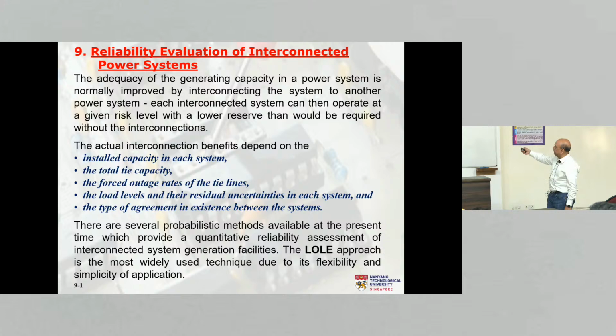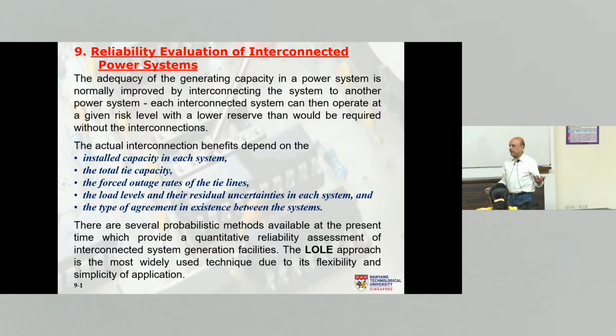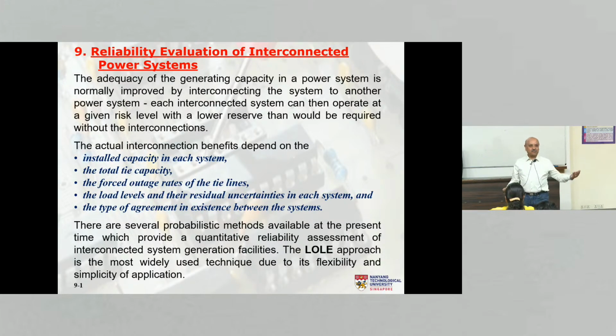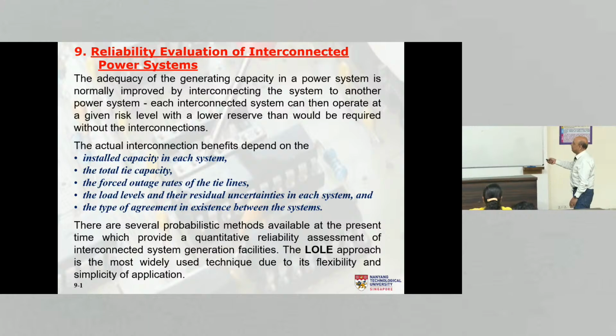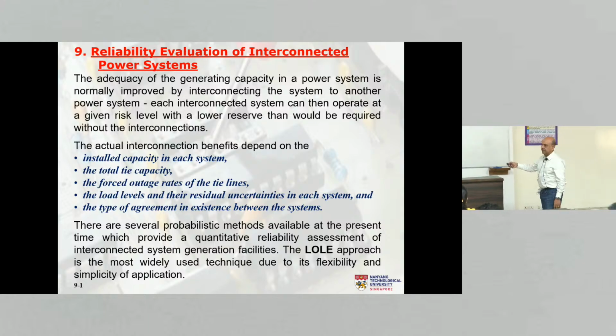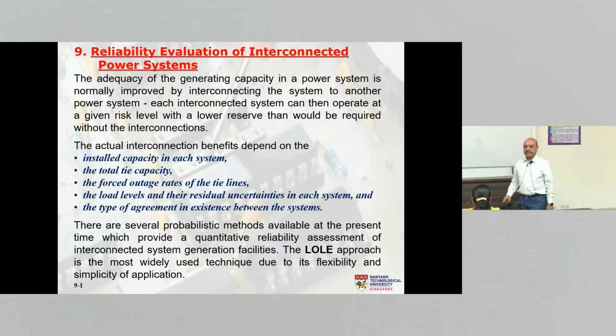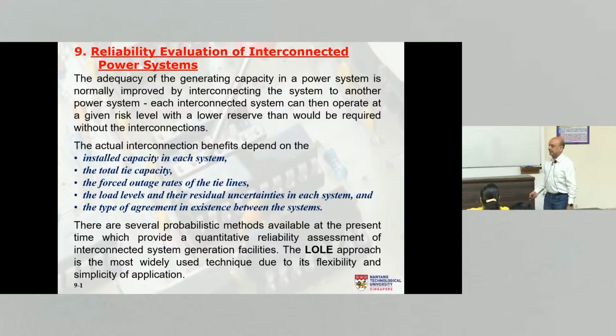So the actual interconnection benefits depend upon some of these factors. The installed capacity in each system. If my system is 10,000 megawatt, and the neighboring system is only 100 megawatt, I wouldn't expect a lot of support from the neighboring system. So the installed capacity is quite a factor. The total tie capacity; tie means the transmission line or the cable between the 2 systems. The capacity of that is limited, like I said, 500 megawatts in this case. It could be lower, it could be higher. So the tie capacity is another factor.